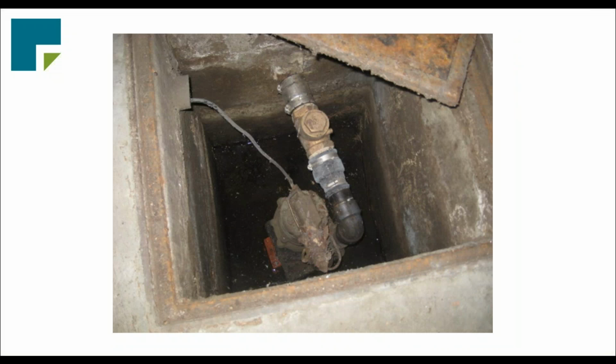In that same garage is a sump pump seen here. This is a common area component that pumps water from a catch pit, the low point of the garage, to the street level drains. Nobody that I met during the site inspection ever heard it run, but the garage has never flooded, so it must be working. The building engineer I met on site said it has never been replaced in the last 10 years since he's been there, and a pump like this typically has a useful life of about 10 to 15 years. So really, the association should be ready to replace it at any time because its life has expired, so we'll set that remaining useful life to 0. The point here is you're going to need to get comfortable making some estimates because we're going to have some uncertainties when we're predicting the future.